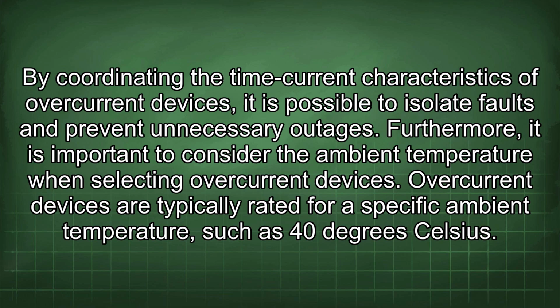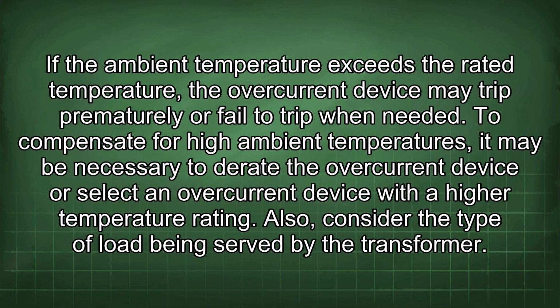Furthermore, it is important to consider the ambient temperature when selecting overcurrent devices. Overcurrent devices are typically rated for a specific ambient temperature, such as 40 degrees Celsius. If the ambient temperature exceeds the rated temperature, the overcurrent device may trip prematurely or fail to trip when needed. To compensate for high ambient temperatures, it may be necessary to derate the overcurrent device or select an overcurrent device with a higher temperature rating.